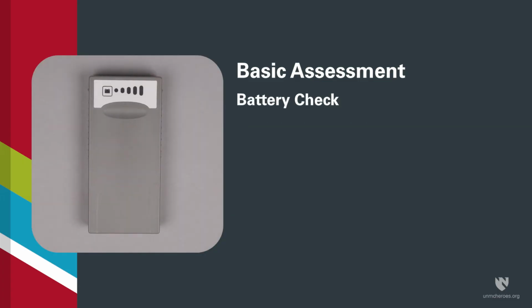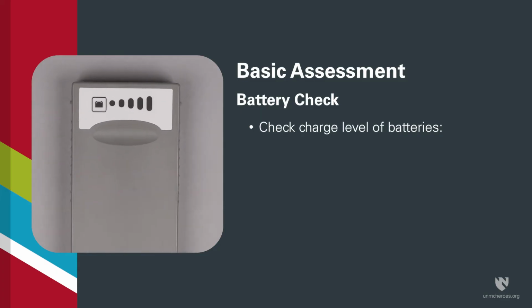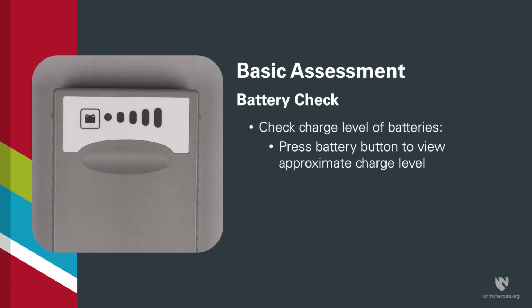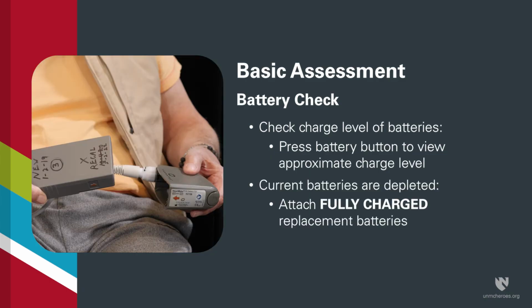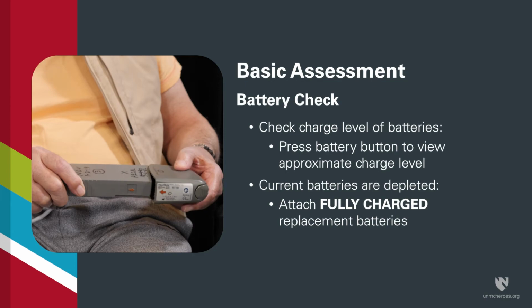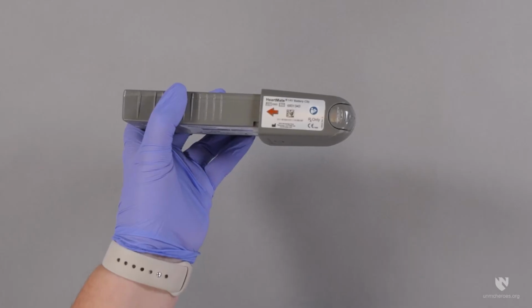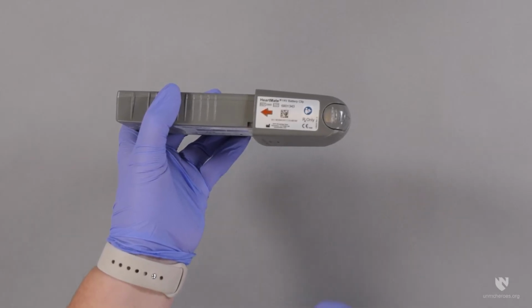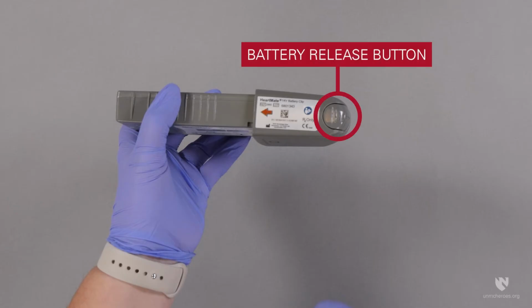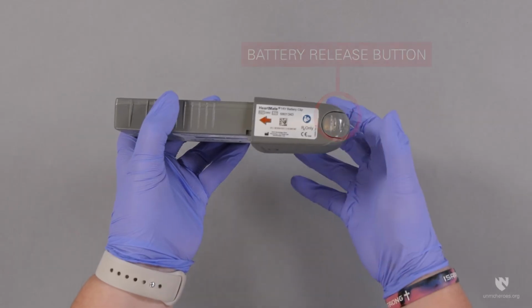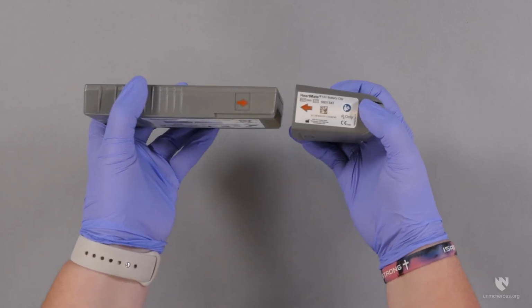Following your patient's physical assessment, check the charge level of the LVAD's batteries to ensure the batteries in use are not depleted. Press the button with the battery symbol to view the approximate charge level of that battery. If the current batteries are depleted, attach fully charged replacement batteries. To attach a replacement battery, first remove the current battery by depressing the battery release button on the battery clip. Then remove the current battery.